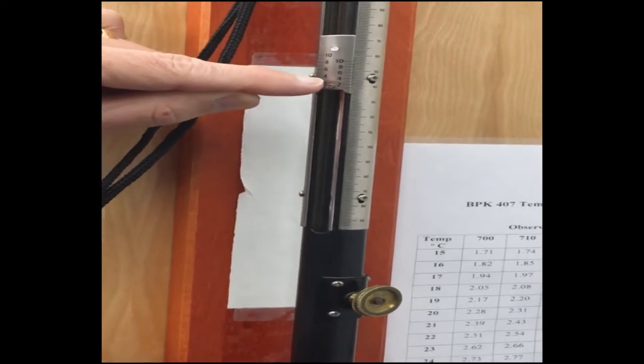The way the vernier scale works is only one of these numbers will line up directly with the line across from that. I look at that, my number 3 is lined up directly with the line across from that. So that gives me a barometric pressure of 737.3.